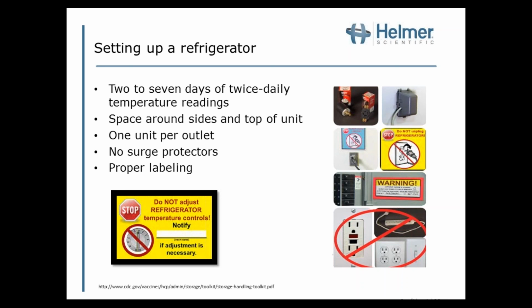CDC recommends 2 to 7 days for this normalization. If you have a backup unit already set and your vaccines are safe there, give the new unit the full 7 days to be sure it's really set up. Units also need space around the sides and top to ventilate properly, and you should only use one unit per outlet — absolutely no surge protectors.